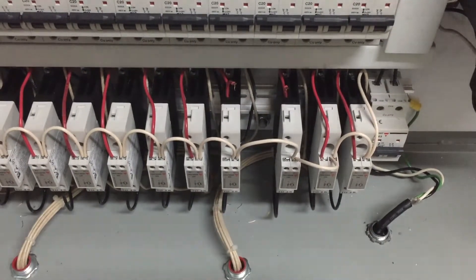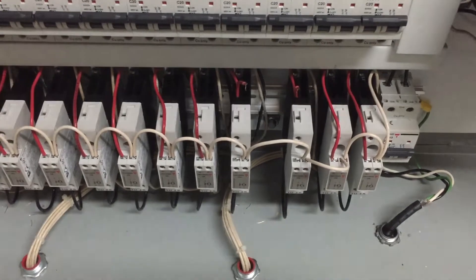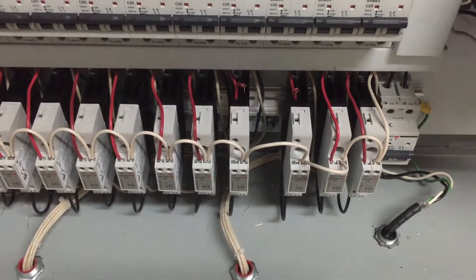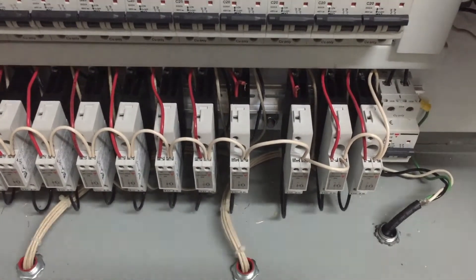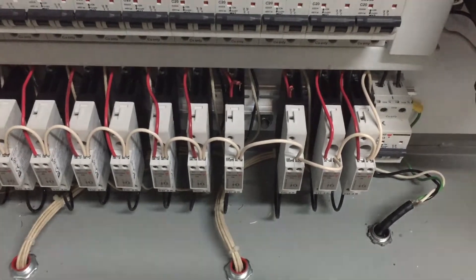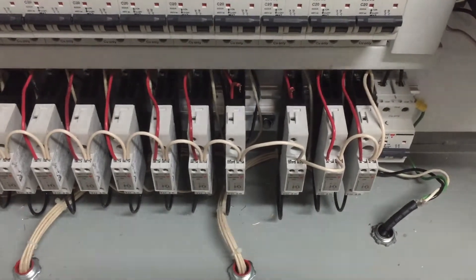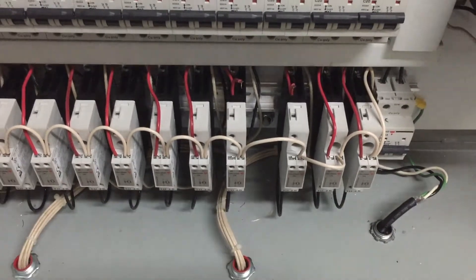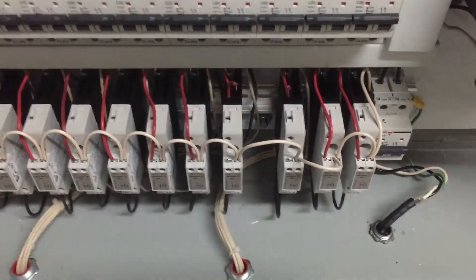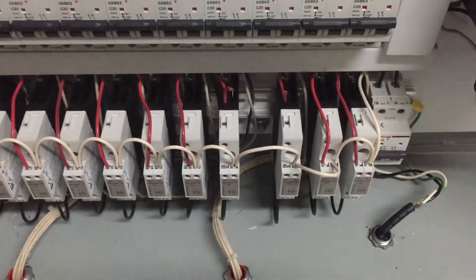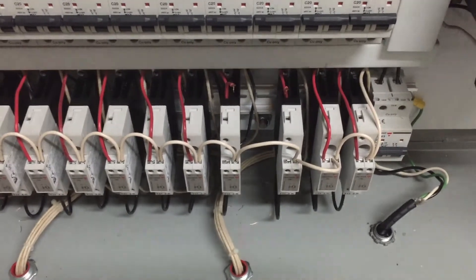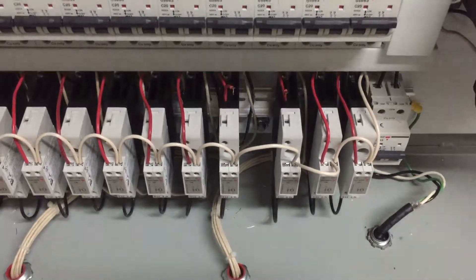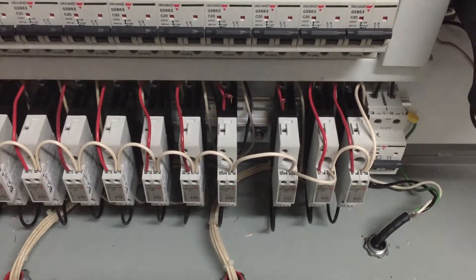I didn't really realize that I was having that problem. I thought everything was pretty good, but when I was running stuff yesterday, I thought something didn't seem right. I took out the heat gun, started temp checking all the heating elements, and oh yeah, they just either were not getting up to the right temperature or weren't really doing anything at all. They only looked warm because of the surrounding heater elements giving them a little bit of heat.